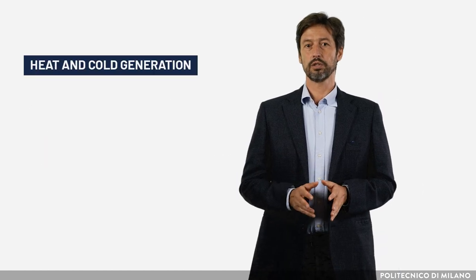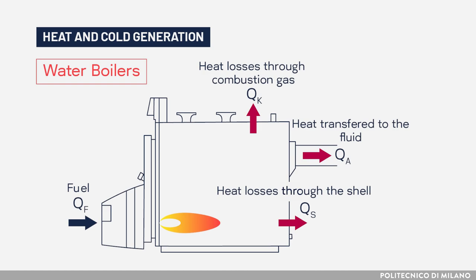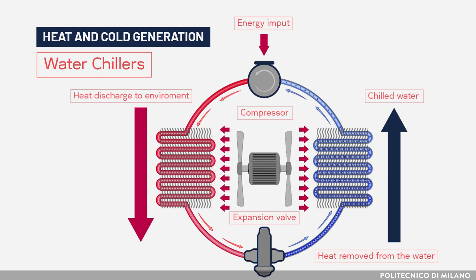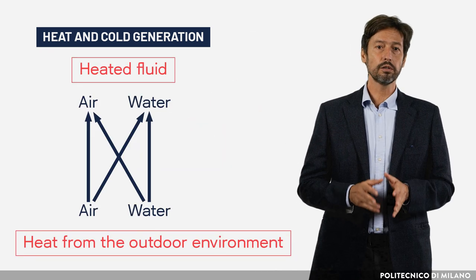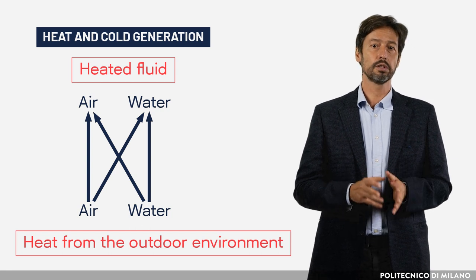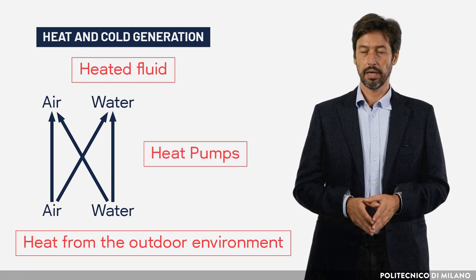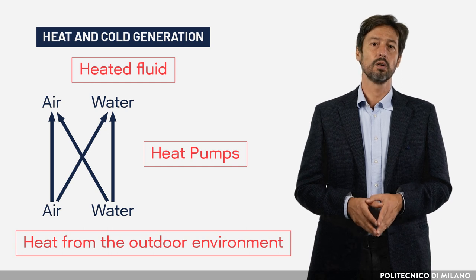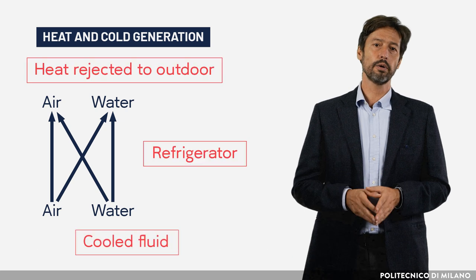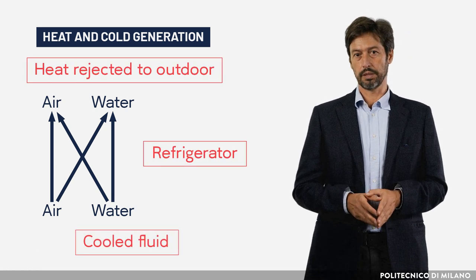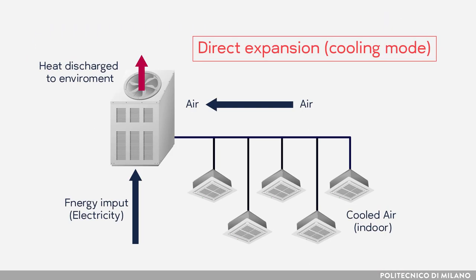Heat and cold generation are provided by water boilers fed by fossil or natural fuels, possibly assisted by solar thermal plants; water chillers fed with electricity or heat, possibly assisted by solar PV or thermal plants; air-to-water, air-to-air, water-to-water, or water-to-air heat pumps fed with electricity or heat, possibly assisted by solar PV or solar thermal plants, which can also operate in reverse mode providing cooling. Additionally, direct expansion chillers or heat pumps are used for refrigerant expansion or compression.